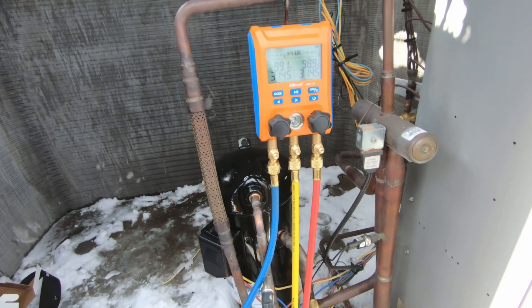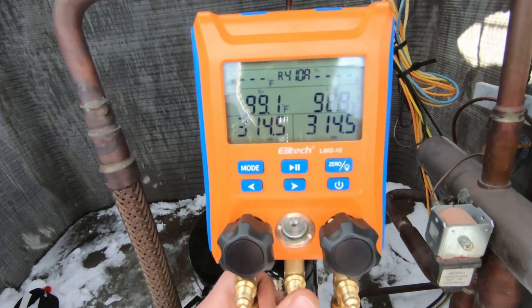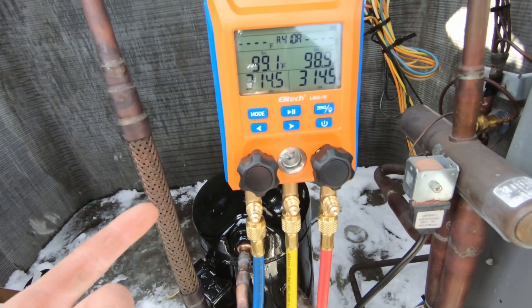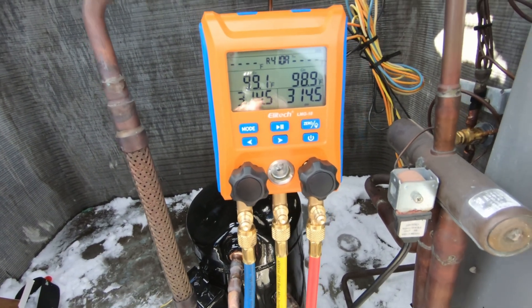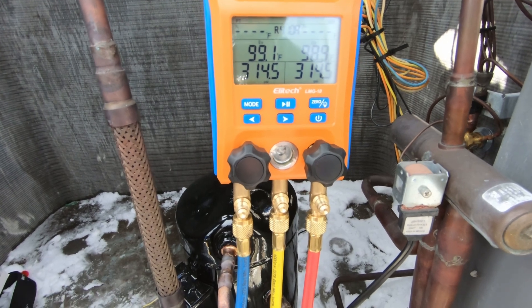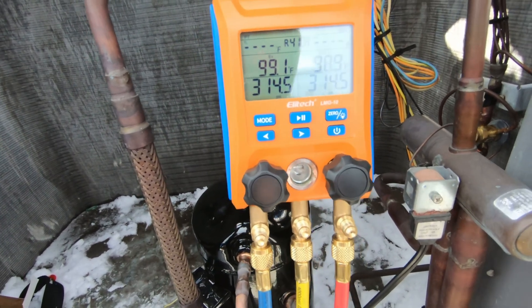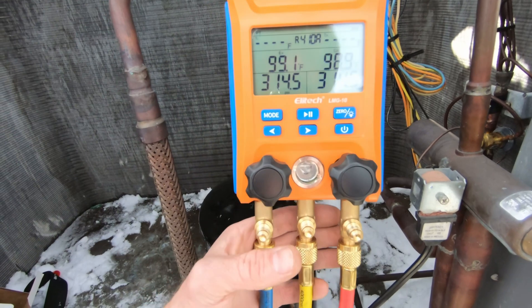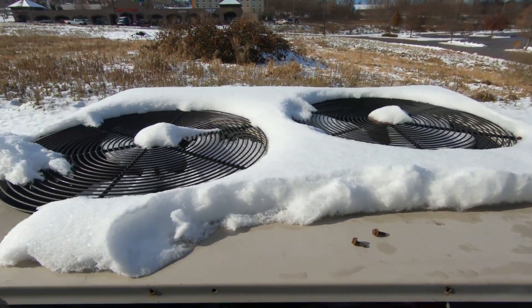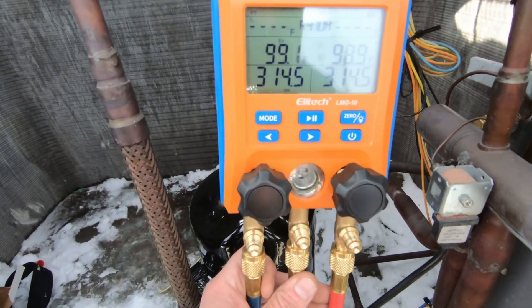All right guys, did a compressor replacement here, some TXVs on this Lennox condensing unit. I wanted to go ahead and show you - I've got a pressure test here. We're holding 314 and a half pounds. Got the new digital manifold here from Elitech, it's the LMG-10, pretty nice - everything's working according to plan. No real issues with anything. It's a nice small compact manifold set for $189 - you can't beat that. Thanks to the guys over at Elitech for sending me this. It's winter now so no issues so far.